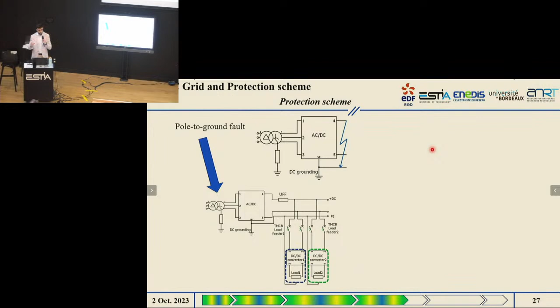And then there is the other perspective of the protection scheme, which concerns the protection against pole-to-ground faults. Once again, we could classify pole-to-ground faults into two great families. The first one is direct contacts, meaning when a user can touch and access an active part of the grid. From our perspective, the best way to protect the system from direct contacts is to use class 2 equipment, meaning reinforced or double insulation for equipment and for the installation.